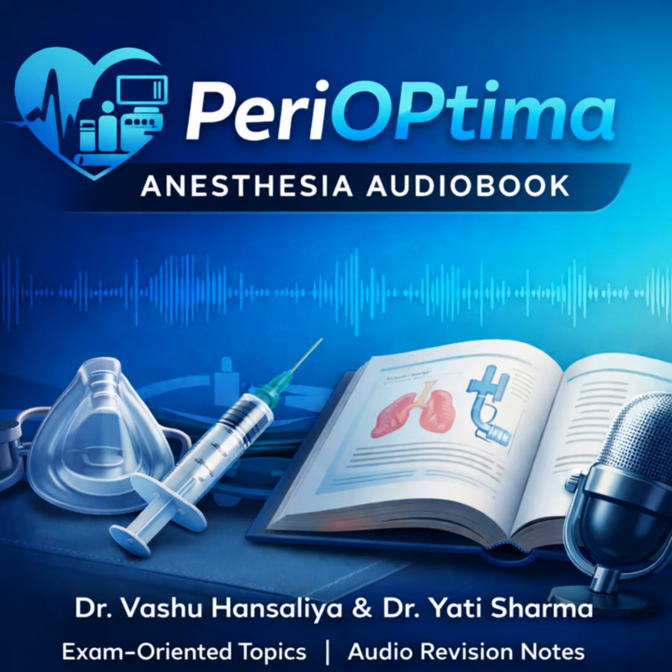So Miller explains that the device measures the baseline impedance of the chest, which is called Z0, and then it looks at the rate of change of that impedance over time. We call that DZDT. So it's not the drop itself, but how fast it drops. It's how fast and how deep that impedance drops with each heartbeat. The algorithm uses that information, aligned with the ECG, to calculate how much blood was ejected. That's your stroke volume. That's incredible. It's basically counting blood cells with electricity.